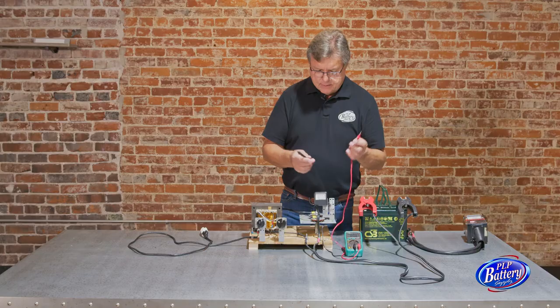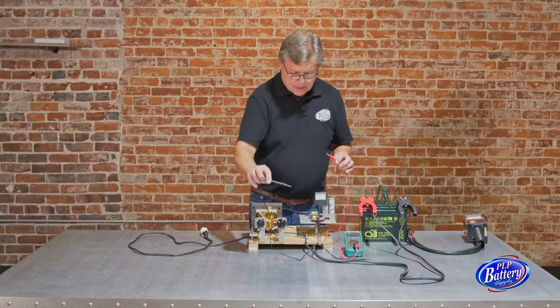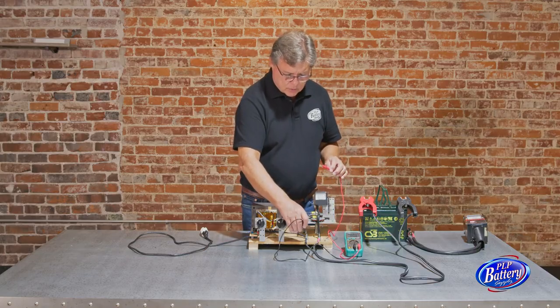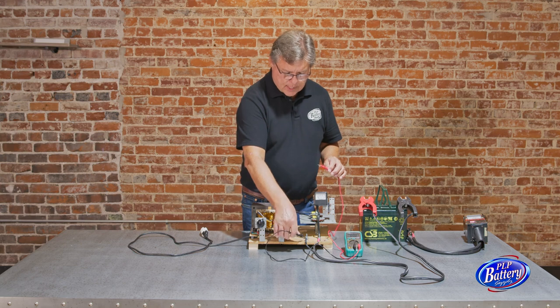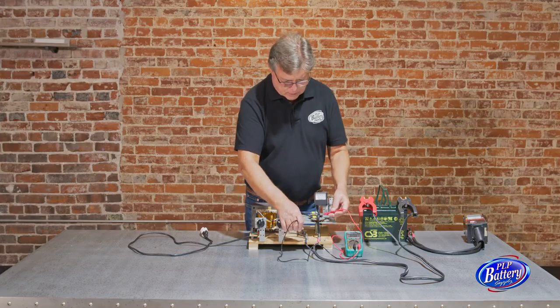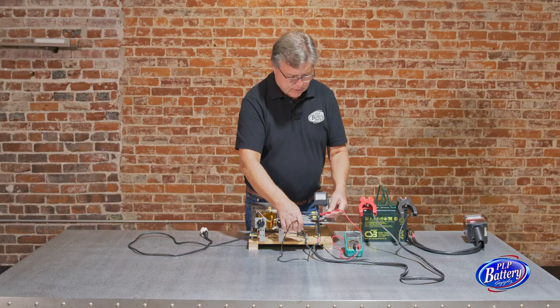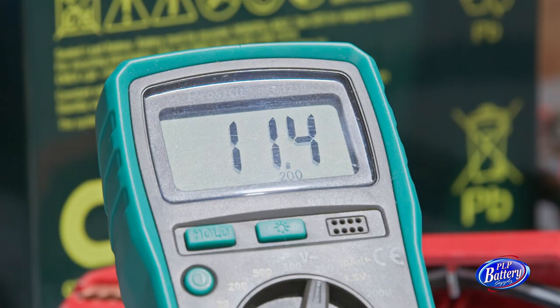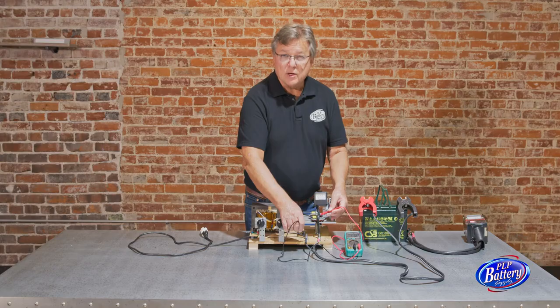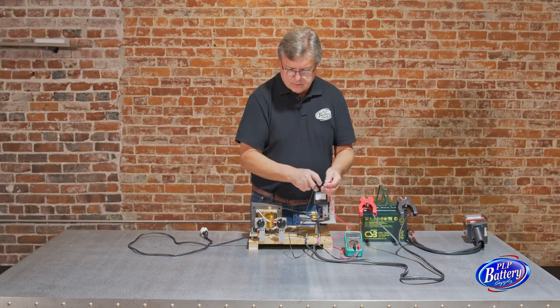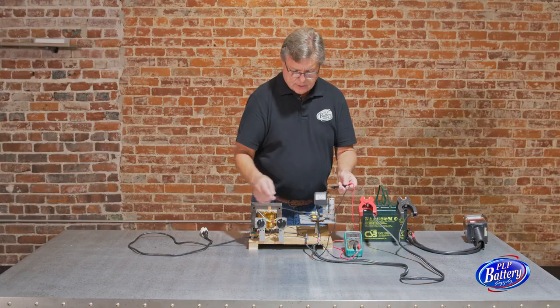So the way to test for that is to probe at the transformer negative output and then test one of your positive outputs where it goes into the rectifier. And this is, again, pretty typical. We've got a reading here of 11.2 volts. So now we're down to about that battery voltage we were talking about before. So it's going in there at 11.2 volts, and that is fairly common.